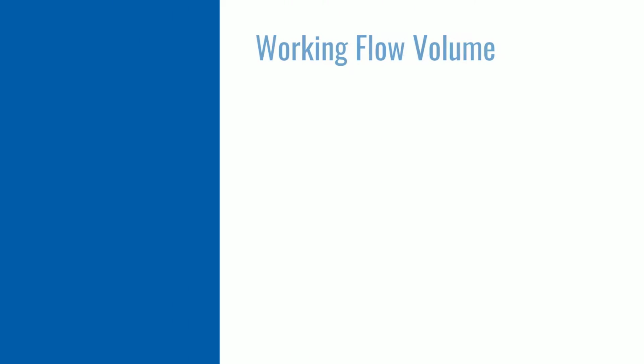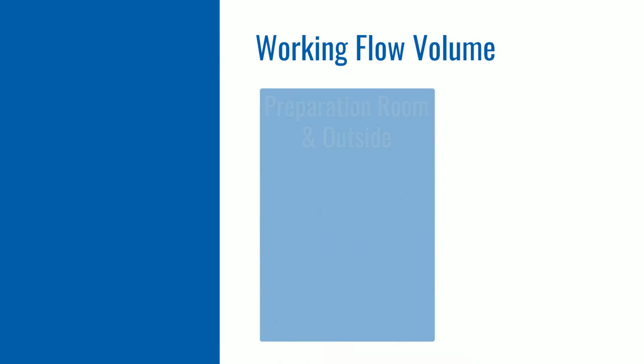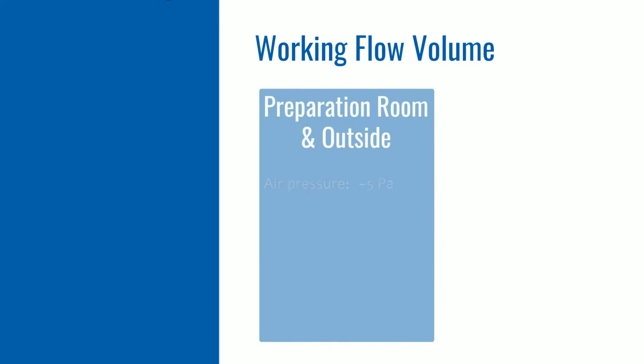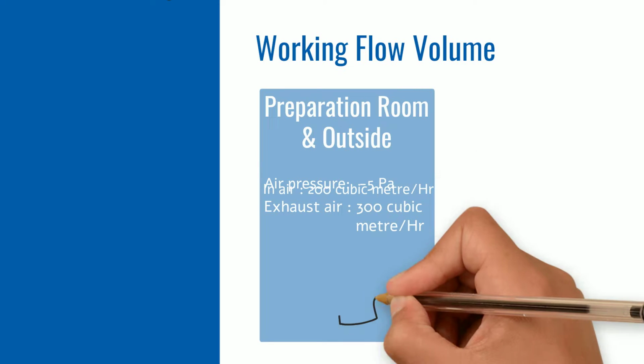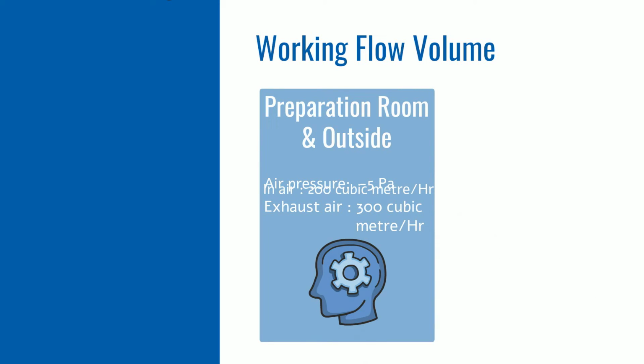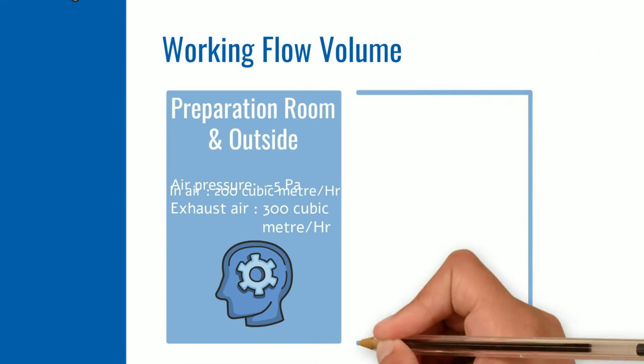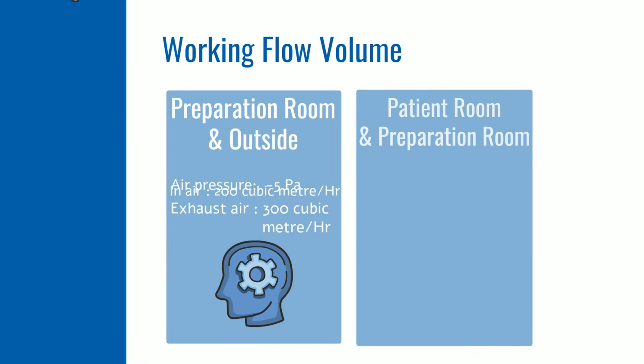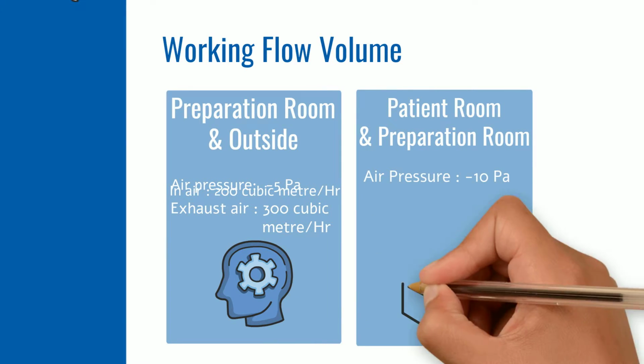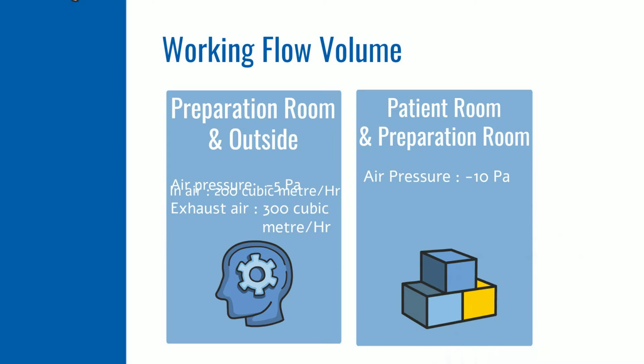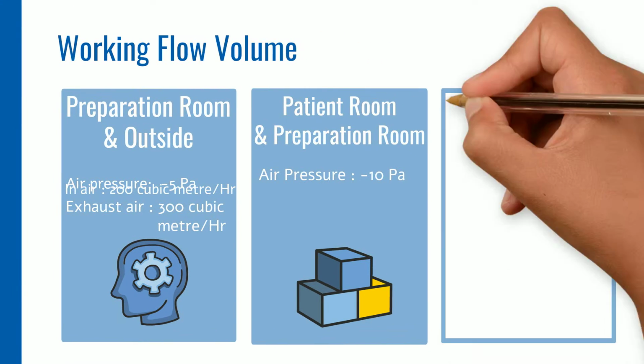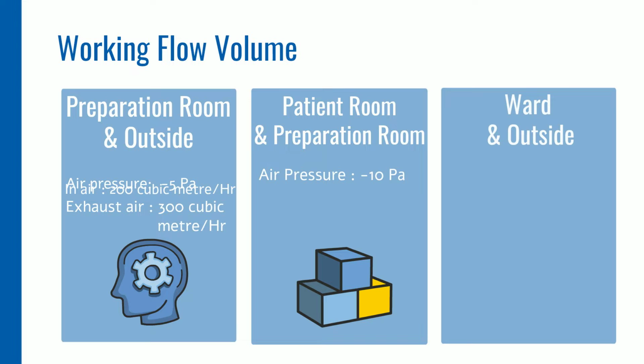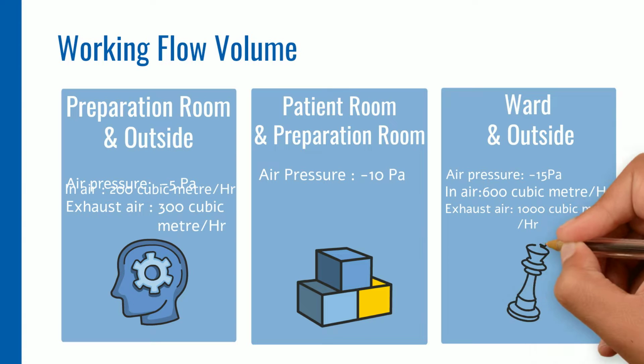For the working flow volume, the air pressure between the preparation room and the outside area is -5 pascals, with intake air of 200 cubic meters per hour and exhaust air of 300 cubic meters per hour. At the same time, the air pressure between the patient room and the preparation room is -10 pascals, which means the difference of air pressure between the ward and the outside area is -15 pascals, with intake air of 600 cubic meters per hour and exhaust air of 1000 cubic meters per hour.